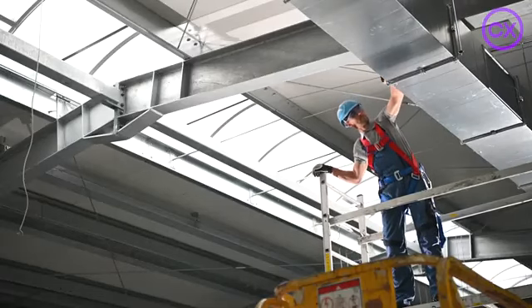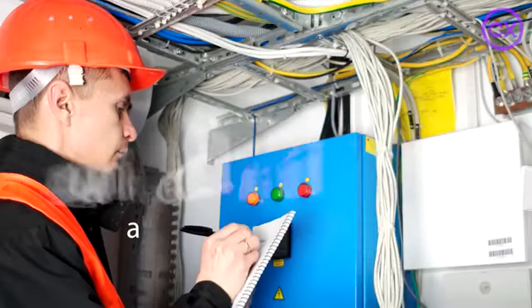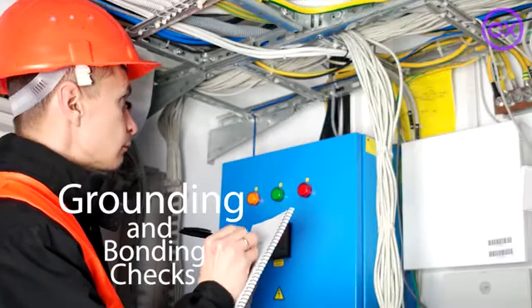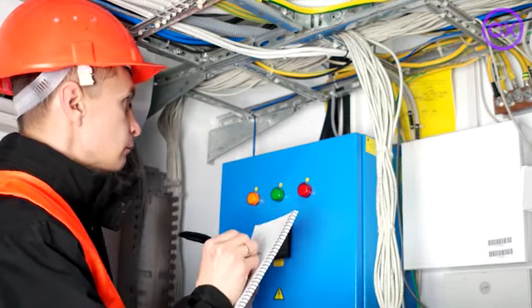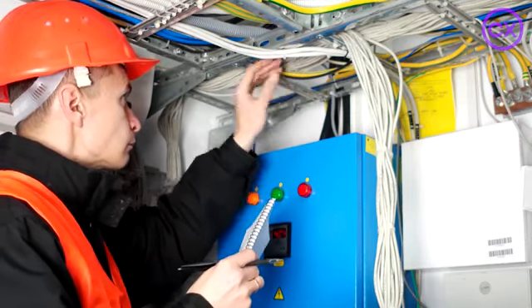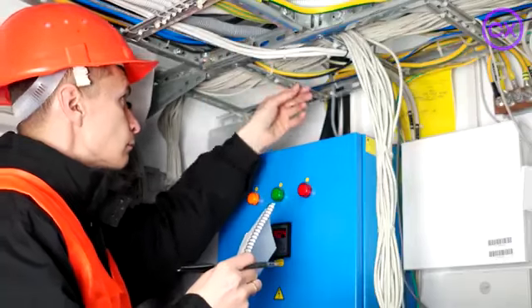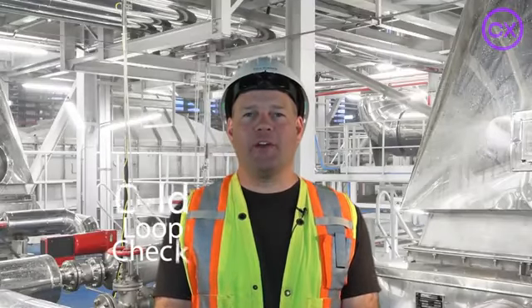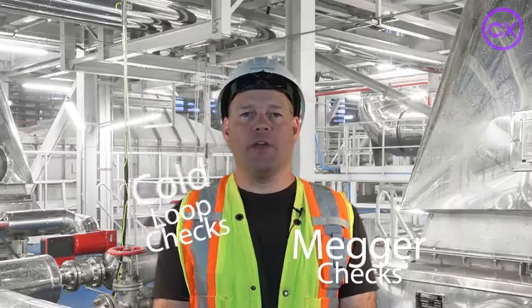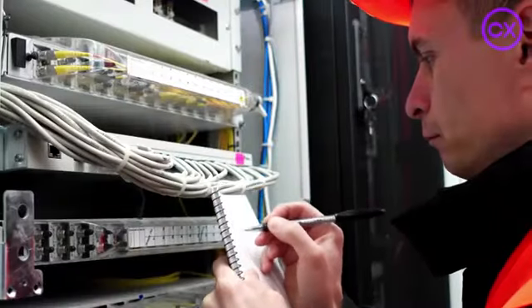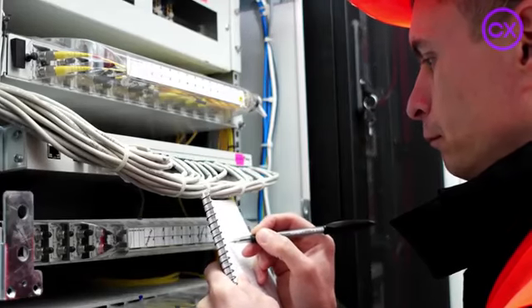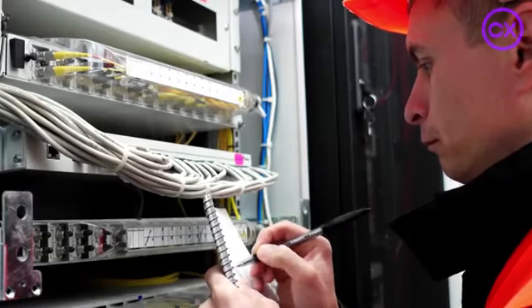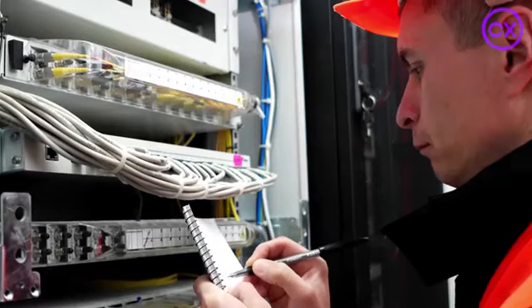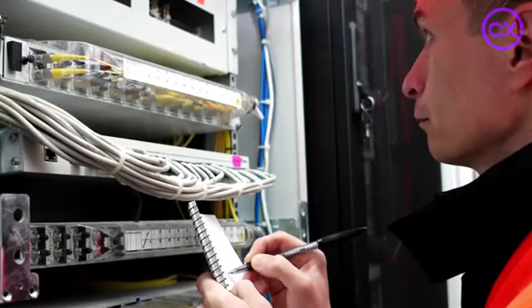Some examples of electrical pre-commissioning activities are grounding and bonding checks to confirm the integrity of the ground system and bonding system by measuring the resistance of bonds to ensure bonding to all metallic surfaces is in place. Cold loop checks and megger checks confirm that all cable and conductors are terminated to the correct terminal blocks. As well, megger checks apply voltage across the cable conductor and insulation to confirm that the cable has not been damaged or punctured to degrade the dielectric properties of the cable.